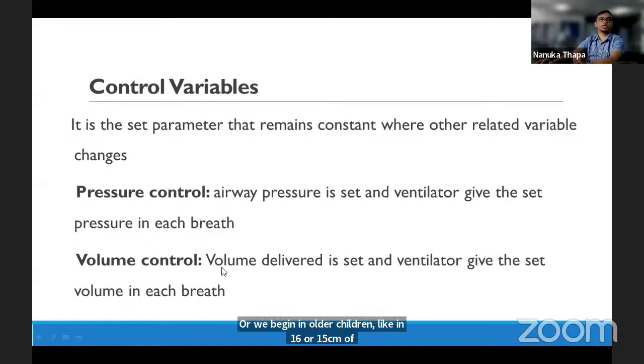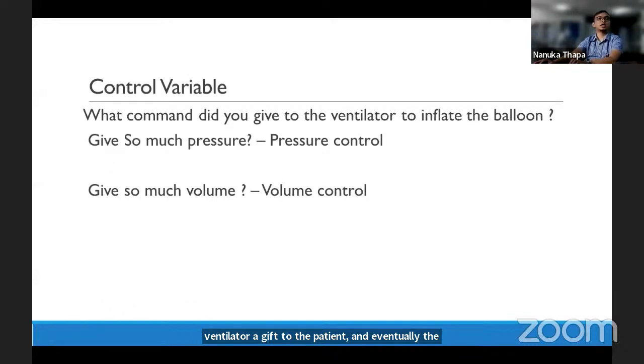Then volume control. Here we set the tidal volume, the volume which the ventilator should give to the patient, and the ventilator gives this set volume in each breath. How much pressure should we give? That is called pressure control. And how much volume should we give? It is called volume control.